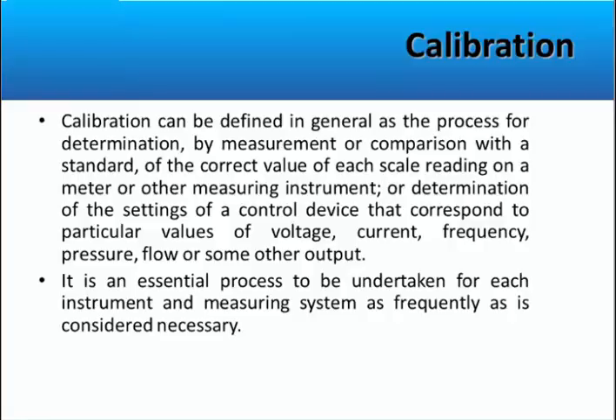That step process can either be conducted out in the field or out of the field in a laboratory or in a shop. Depending upon the criticality of the system, the required level of verification and calibration, it becomes important to take it out of service or out of the field. One general rule is that only relatively low accuracy verifications can be done out on the shop floor. For higher level and critical systems, and ones that generally require mandatory points, you need to take them back out of the field and into a laboratory or a shop that is able to do the system.